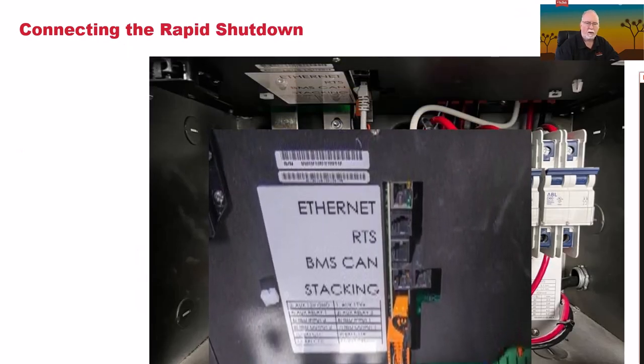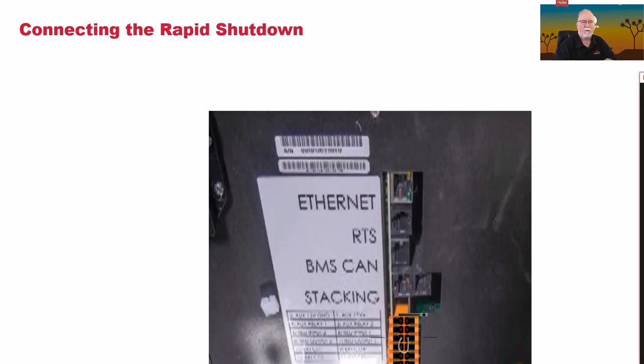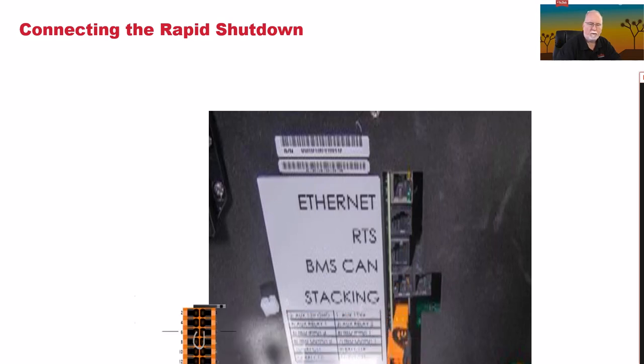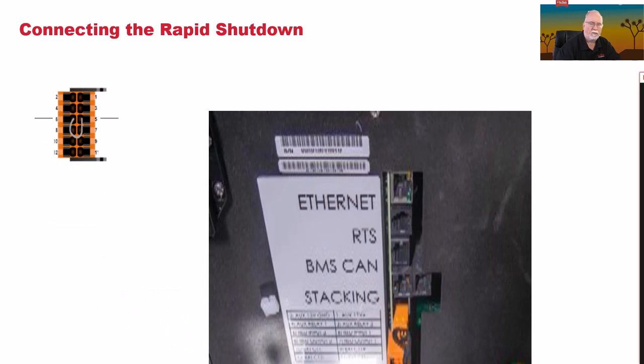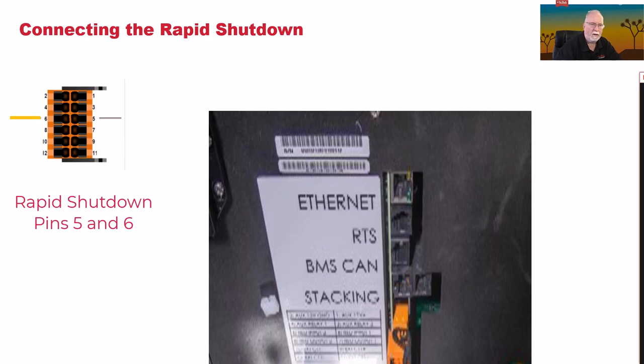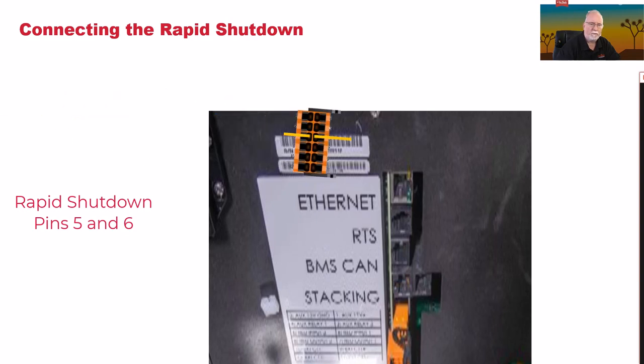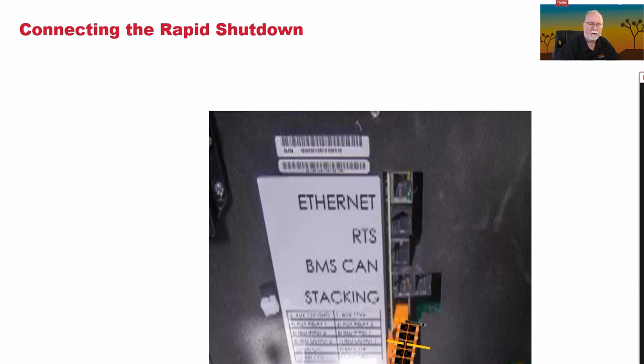So kind of looking at how we're going to do this, if you rotate down that top panel, I'm just looking at it from looking up. There's a multi-connector that's in the very back of the panel. Just take that multi-connector out, put it where you can see it. There's going to be a jumper that's going to attach the rapid shutdowns. So what we're going to do is remove that jumper. We're going to install our wiring between pins 5 and 6, by pushing in the little tabs, inserting the wires as needed, and then we're going to reposition this back, plug it back into the system. Now my rapid shutdown is in place.